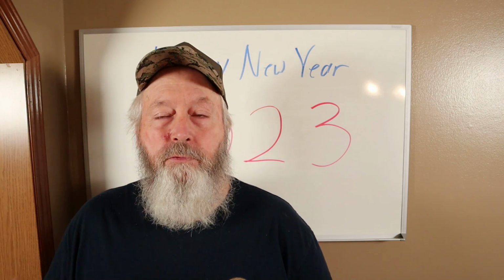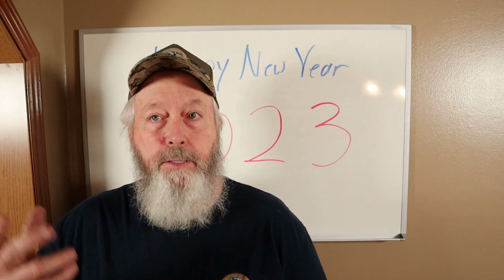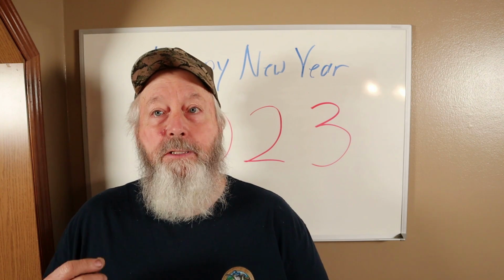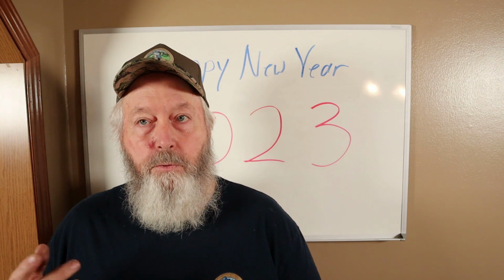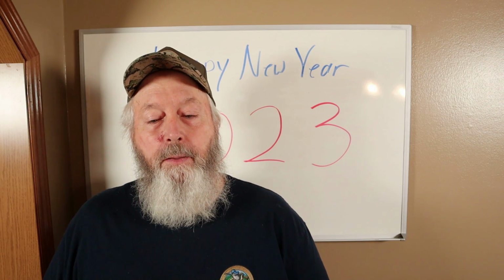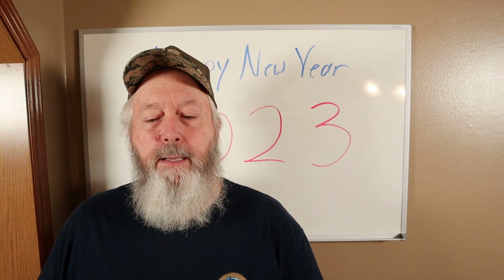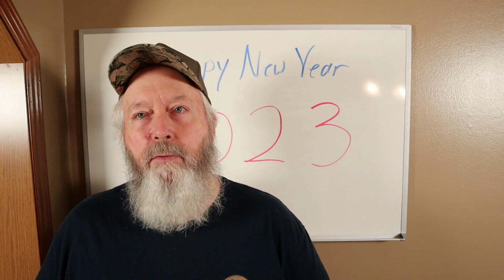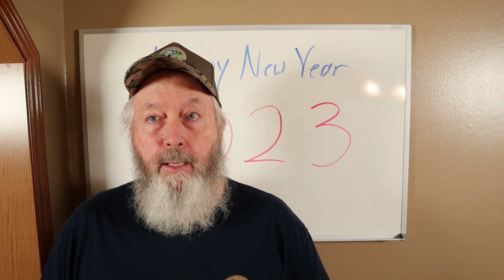Quick Google search just before I turned the camera on. Natural gas, now it gets different, is 6 to 7 water column inches. And of course, propane is 11 to 14. That 11 to 14 water column inches works out to about 0.4 to 0.5 psi. Okay. Why do you have a pressure regulator?